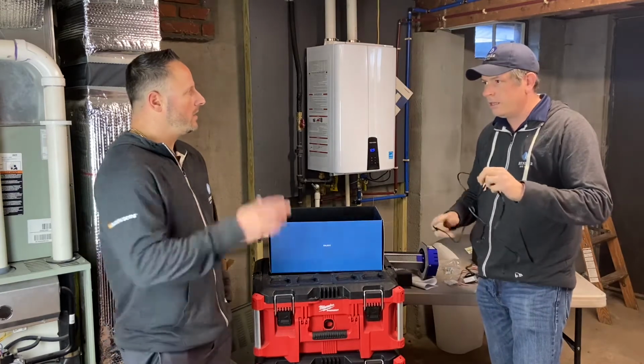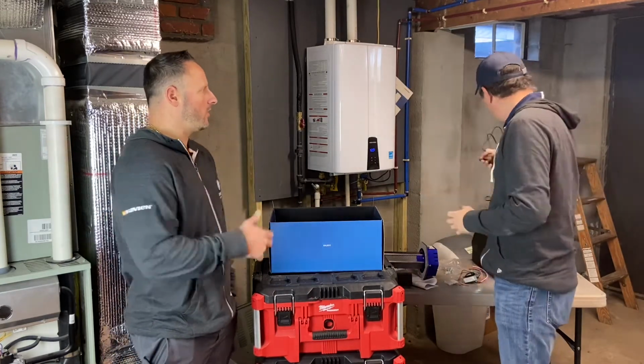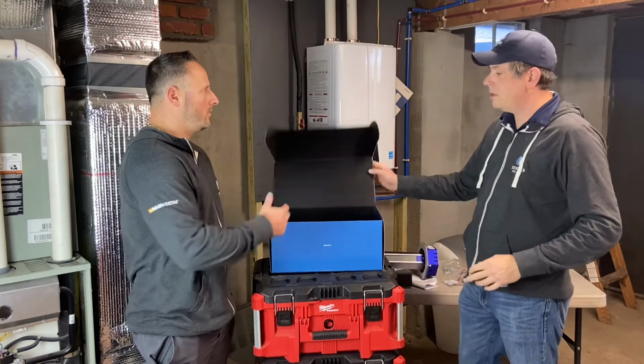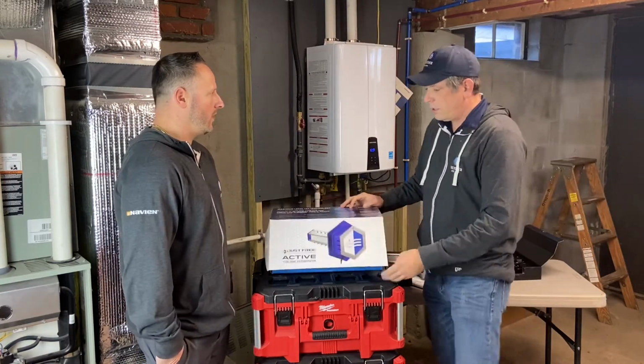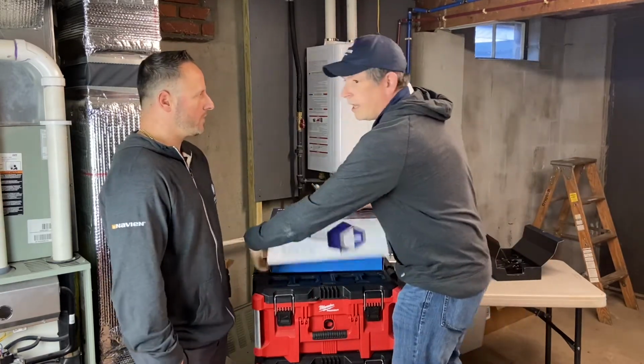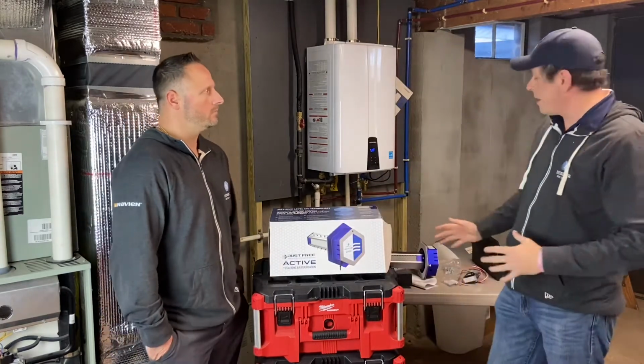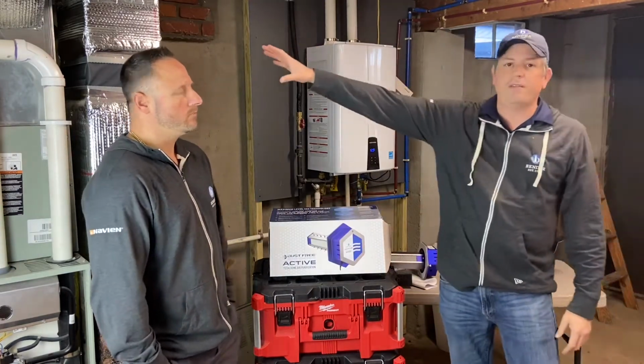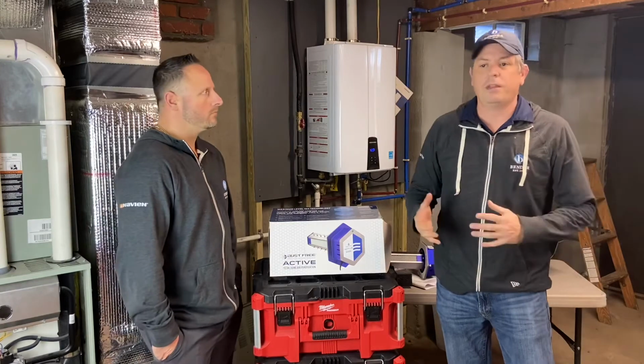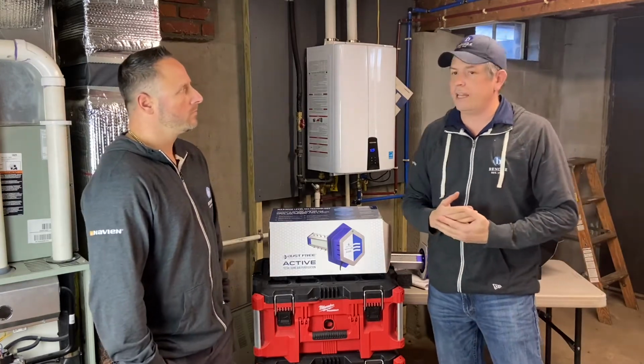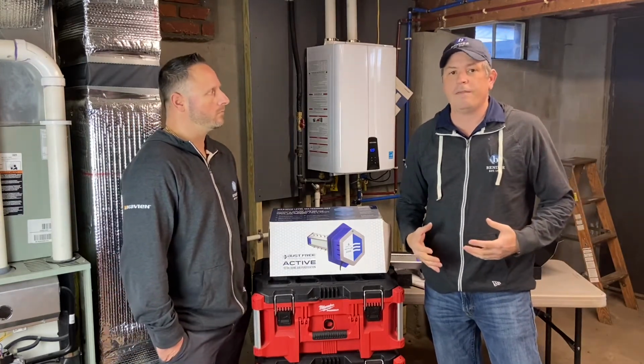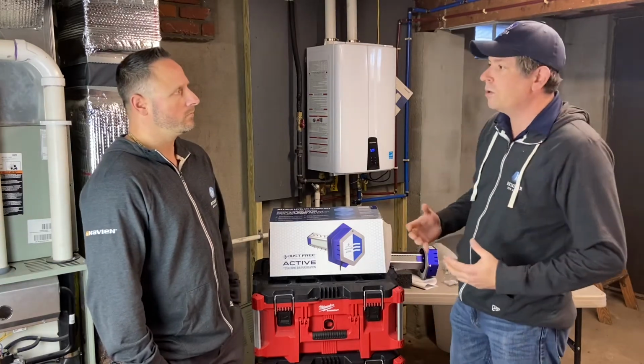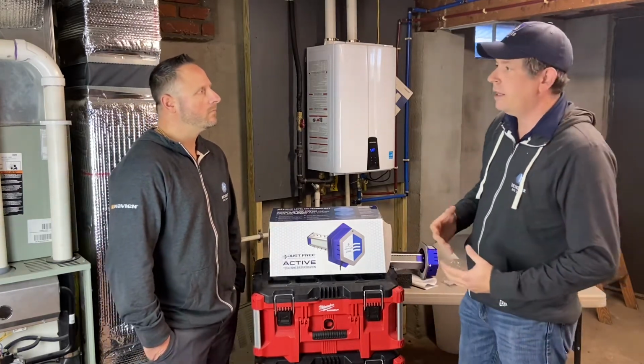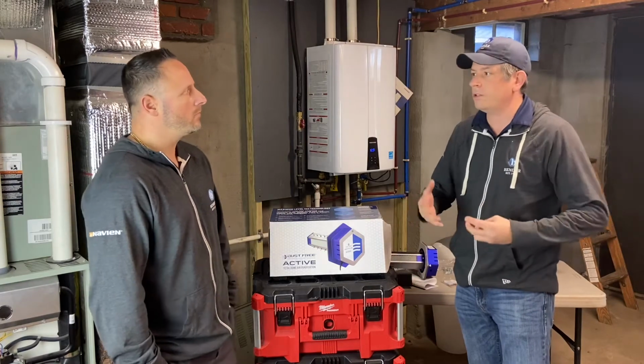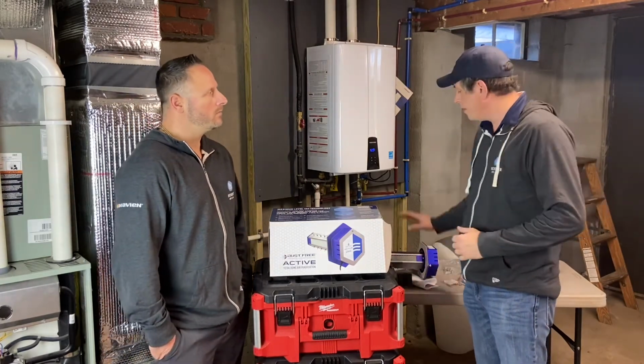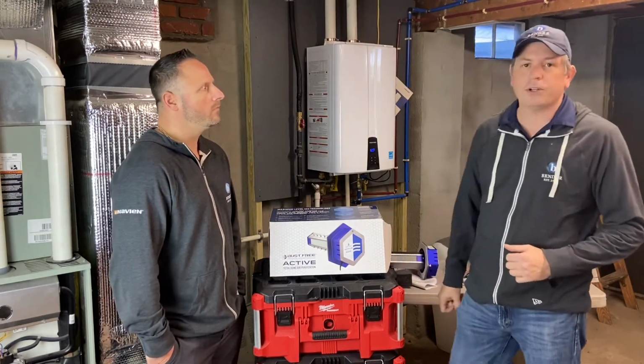Now Mike, before we get into the install, where is the recommended area of the system to put this? So the best place, as they recommend in the instructions, is above the evaporator coil. Because now you're doing two things - you're helping ionize and oxidize the air, and you're also keeping the evaporator coil clean of mold or anything that could build up on it in the off cycle when it's still wet. So that's the best place, but you can put them in the return as well.